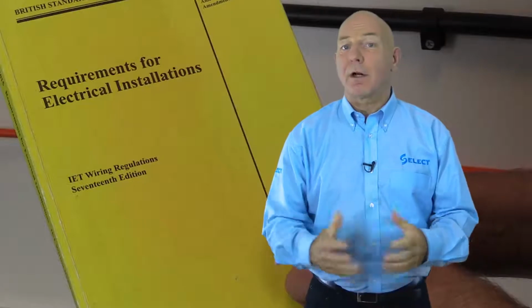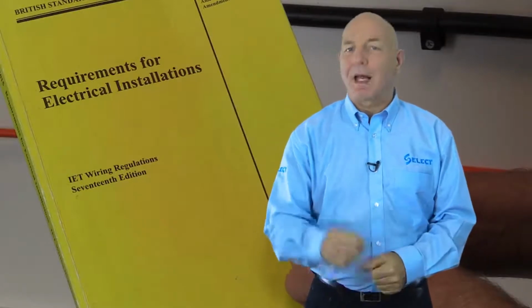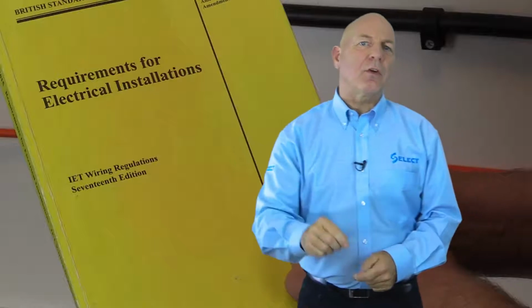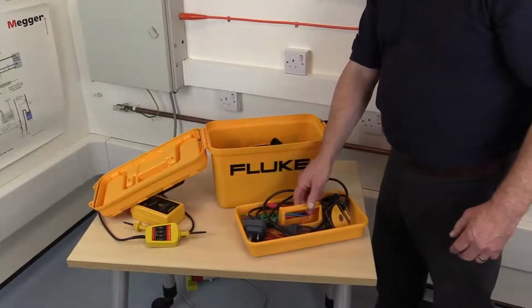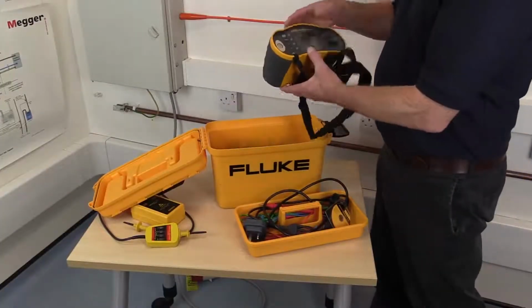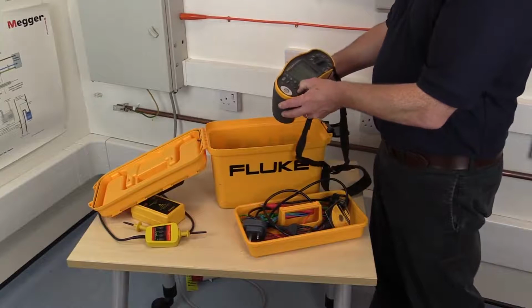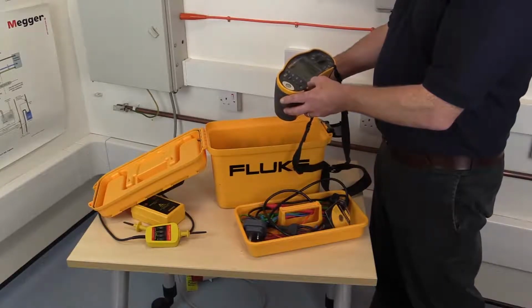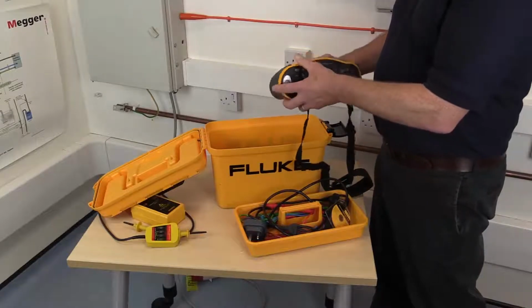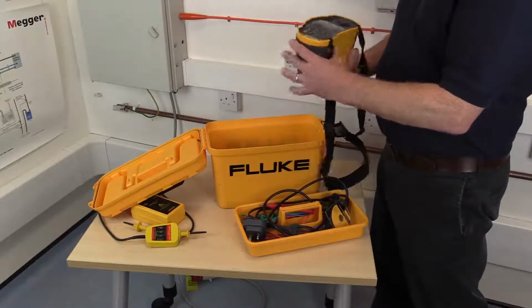Specifically, it's important that he or she has a good working knowledge of the actual version of BS7671, current at the time of the work, and particularly that the person is fully conversant with the inspection and testing process required. Next, consider the suitability of the test equipment and the test leads to be used. It should be confirmed that the test equipment conforms to BS EN 61557 and that it's in good working order.